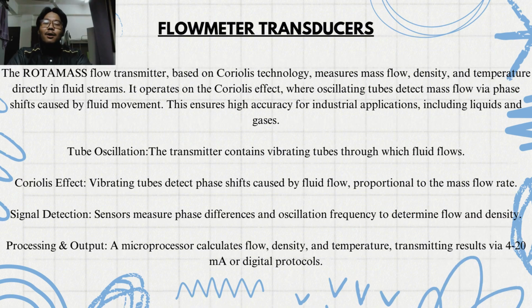So, I will present about the flow meter transducer. The flow meter transducer is based on Coriolis technology and measures mass flow, density, and temperature directly in fluid streams. It operates on the Coriolis effect, where oscillating tubes detect mass flow via phase shift caused by fluid movement. This ensures high accuracy for industrial applications, including liquids and gas.